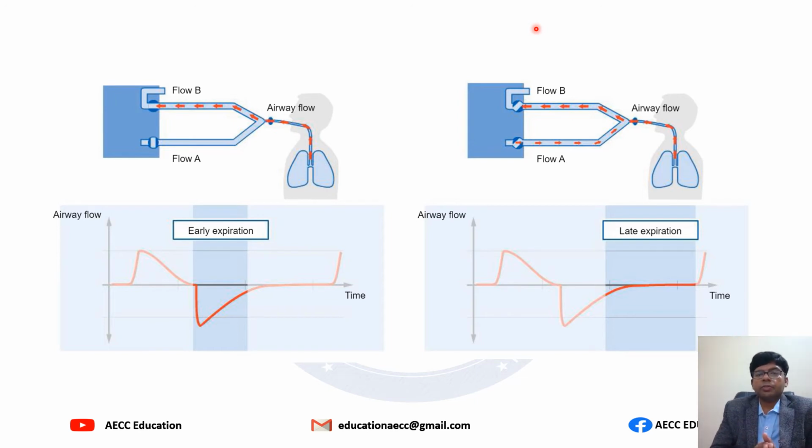If the patient inhales, a part of the gas flow goes to the patient, resulting in an inspiratory airway flow drop, and there is a discrepancy of the flow between the inspiratory limb and expiratory limb that will be sensed by the ventilator, and by sensing this, the ventilator delivers the preset breath.